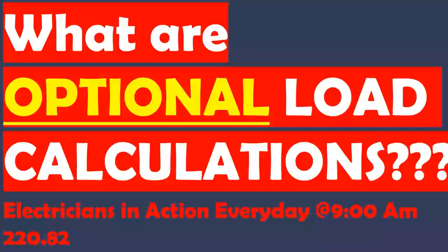In the field, typically people will use the optional method because it gives you a lower calculation — typically a lower amp calculation — which may allow you to size a smaller service, use smaller wire, and use smaller pipe.